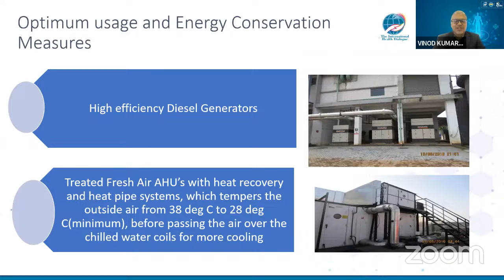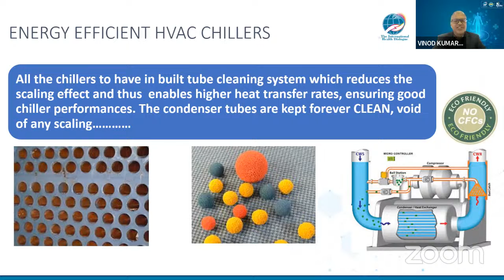Now, coming to the chiller plant, it is the biggest energy consumer in the hospital. You need to ensure higher and better heat transfer. To make sure of that, we should not have scaling. Whenever there is a water source, obviously scaling happens. To reduce the effect of scaling, we need automatic tube cleaning systems, which will keep on cleaning the condenser tubes at regular intervals. This will keep the tubes very clean and void of any scaling, which generally gives you better heat transfer rates.